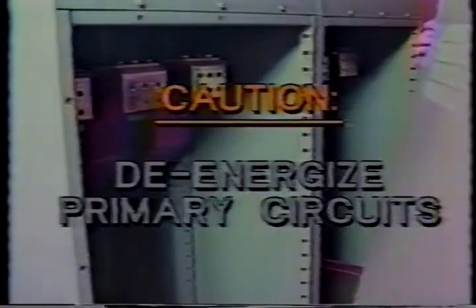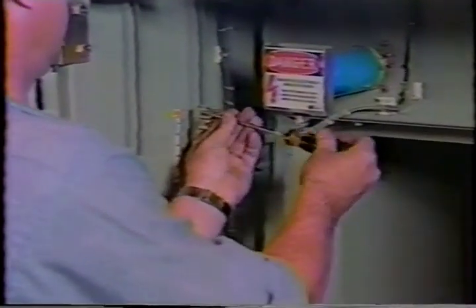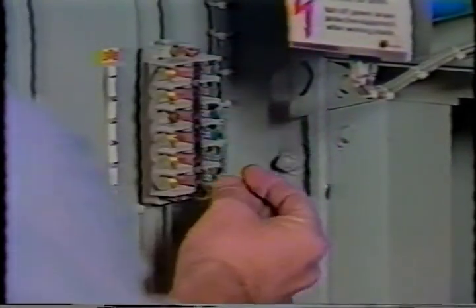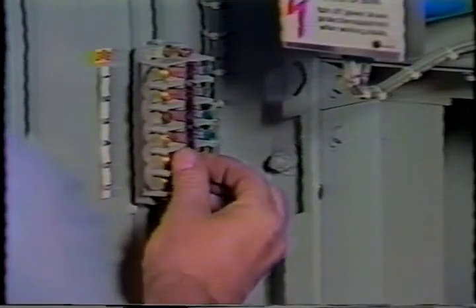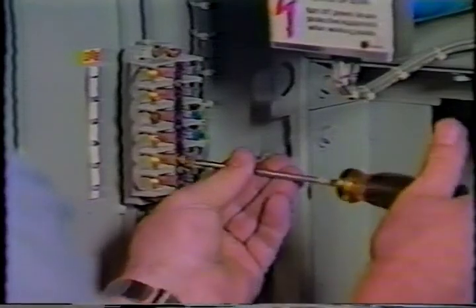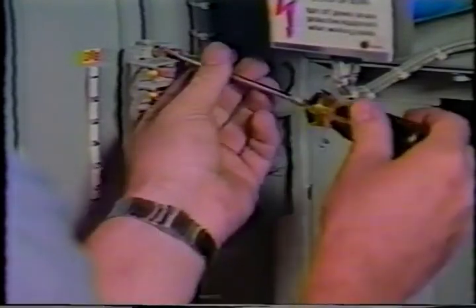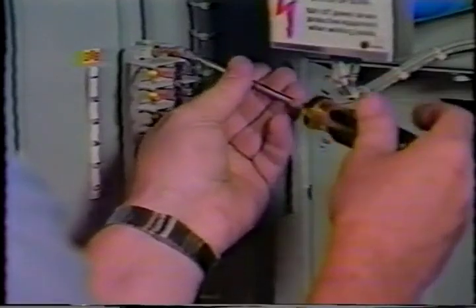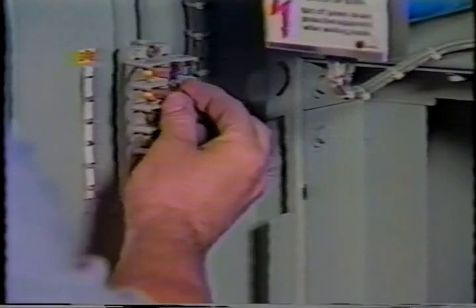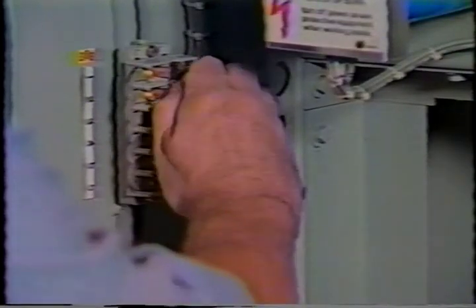Before removing a bolted-on cover, first make sure that all the circuits have been de-energized. Never try to disconnect or open the secondary circuit of a current transformer that is carrying load. In this situation, the transformer develops a dangerously high voltage. Before attempting work, either de-energize the circuit by opening the breaker or short-circuit the secondary of the current transformer.